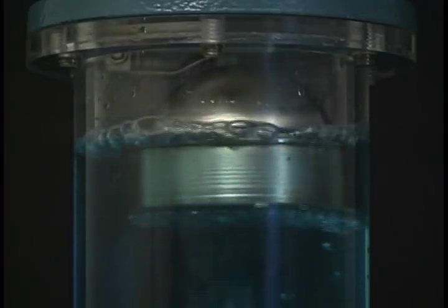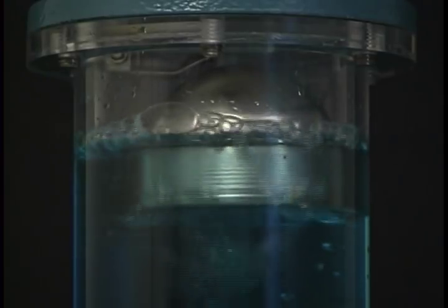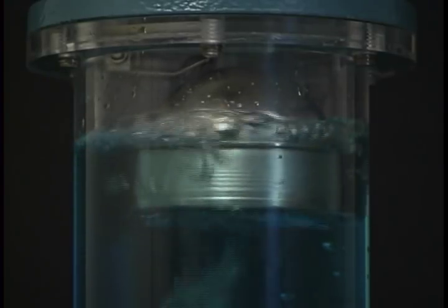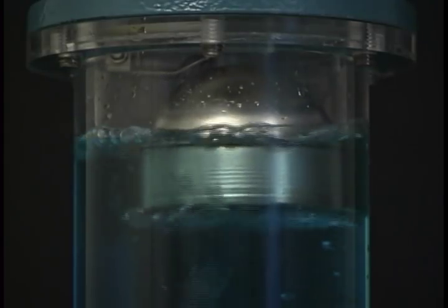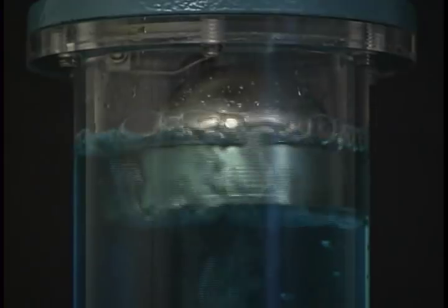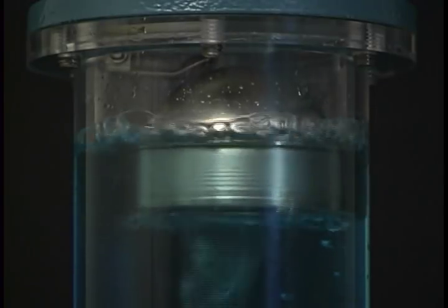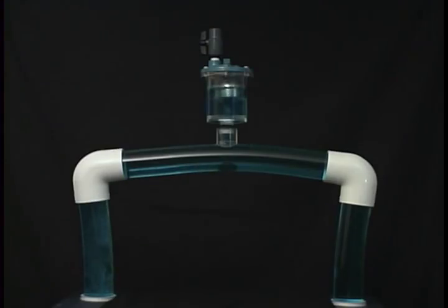As air accumulates, the valve will continue to cycle in this manner to remove collected air. You can see how the type 316 stainless steel float fluctuates to allow air to be vented while the water is contained. An air release valve will continue to open, releasing air during system operation, because forces acting to open the valve are greater than forces acting to hold the valve closed.